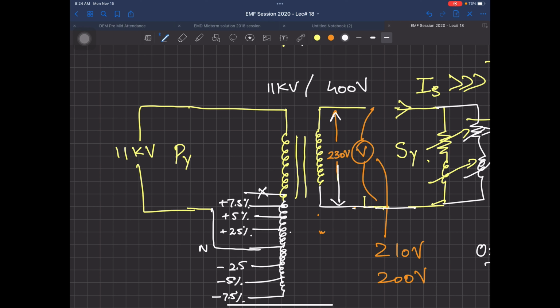If you want to increase the voltage by 2.5%, you connect to that tap; if the voltage regulation needed is more, you connect further along. These six taps - three plus and three minus - are normally provided at all grid station transformers that convert 11 kV to some other voltage, or convert transmission line voltage from 33 kV to 11 kV.